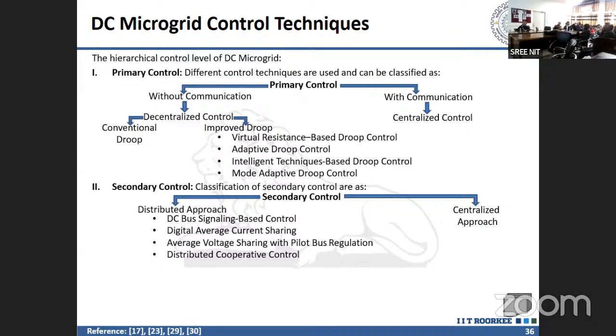In case of AC microgrid control, there are two parameters which are mainly to be controlled: voltage and frequency. In DC, we normally have the voltage to be controlled. So conventional droop, improved droop which is your virtual resistance, adaptive droop control, intelligent technique, mode adaptive droop control - what is droop? We will discuss just now. With communication, we have the centralized control, and similarly for secondary control, we have the distributed approach with these four types of controller.